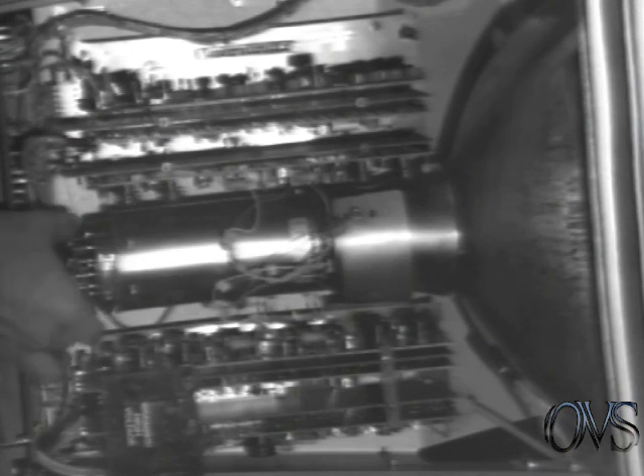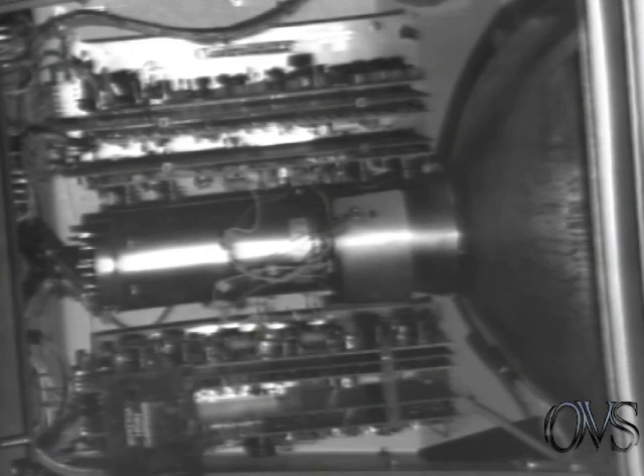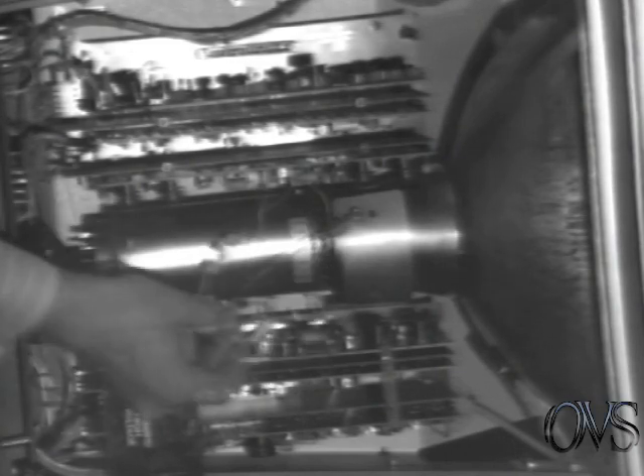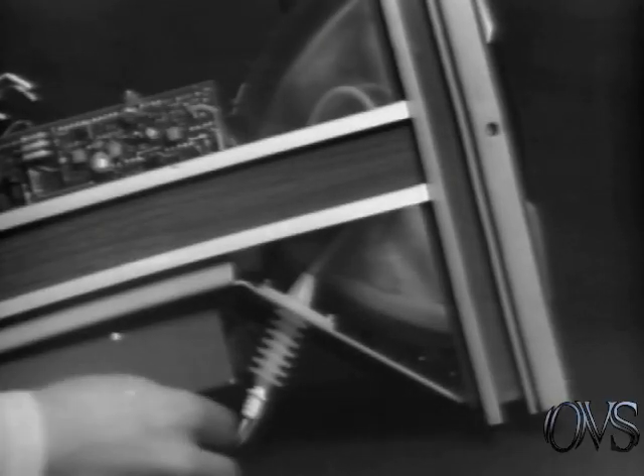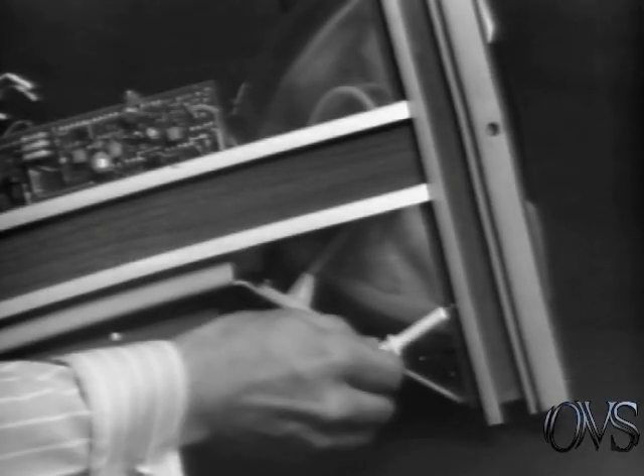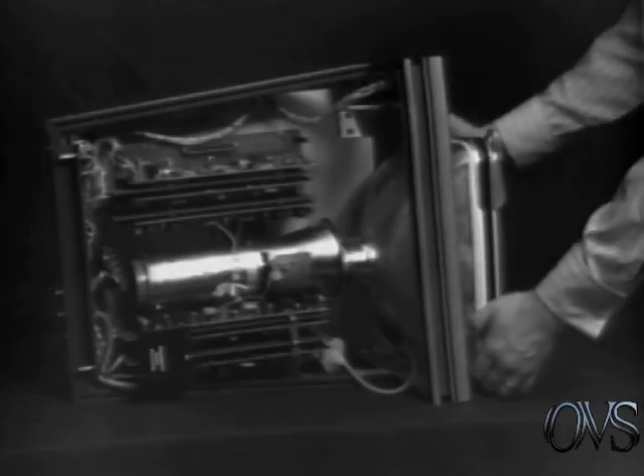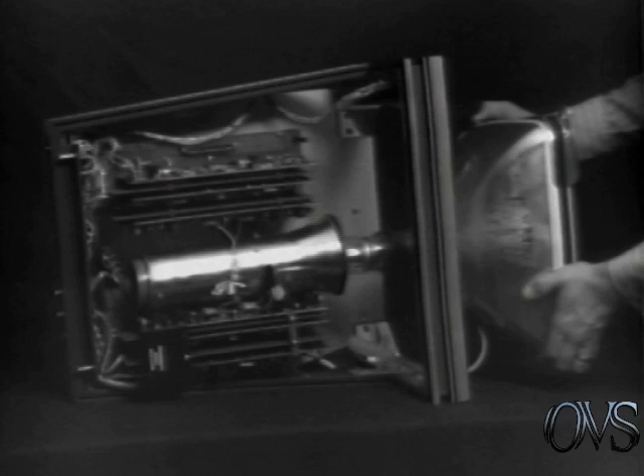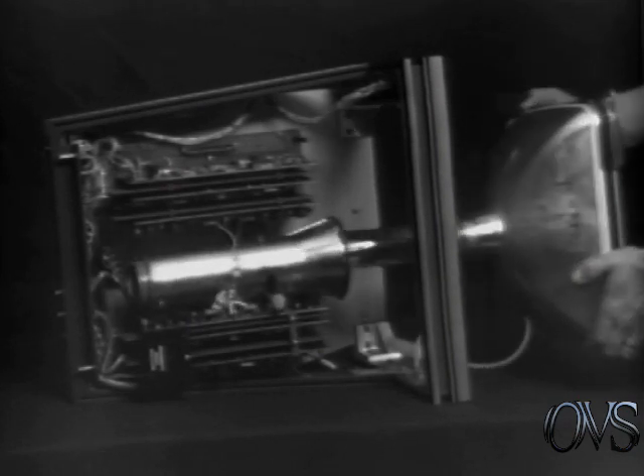First, remove the CRT base socket and loosen the clamp. Next, disconnect the neck pins. Disconnect the post accelerator lead and immediately discharge it to ground. Remove the screws attaching the post accelerator connector to the deck. Remove the plastic mask and the 4 screws that attach the CRT to the front of the instrument. Now carefully slide the CRT out, being careful that the neck pins don't catch on the coils located inside of the shield.